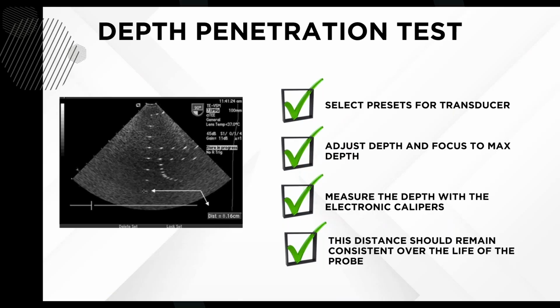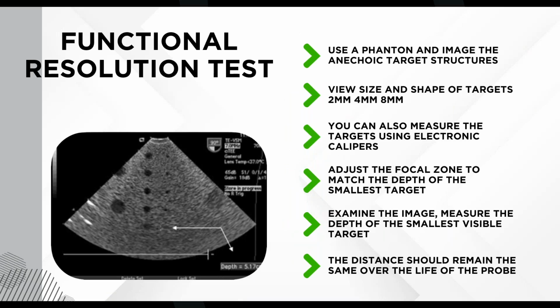The next test is the functional resolution test. This is the functional resolution test, what it's going to look like when we put it on the system here. We're going to use phantom image and anechoic target structures, which is these guys over here on the right here. We're going to view the size and shape of the targets. Typically, they're 2, 4, and 8 millimeters in distance here.